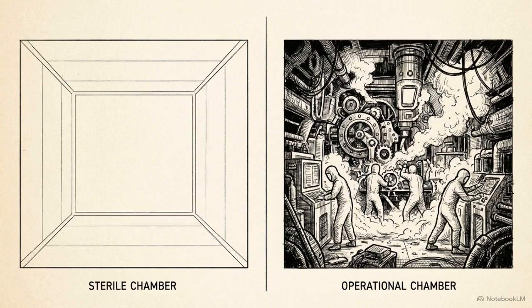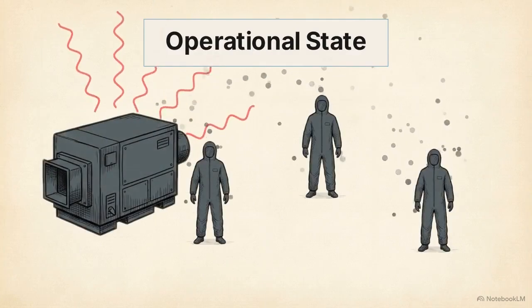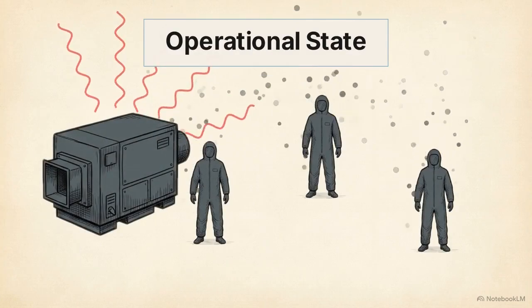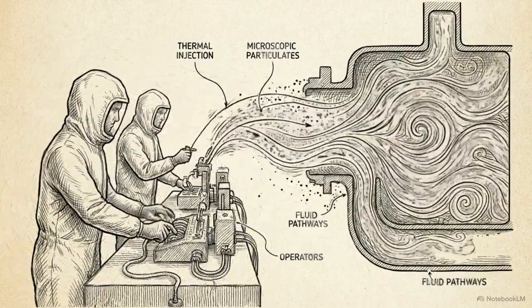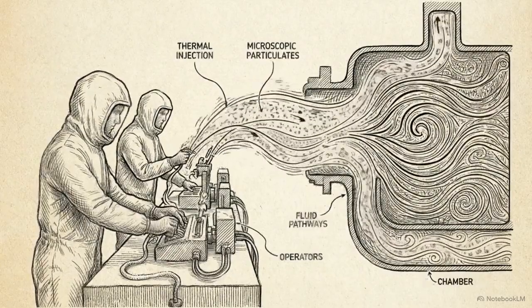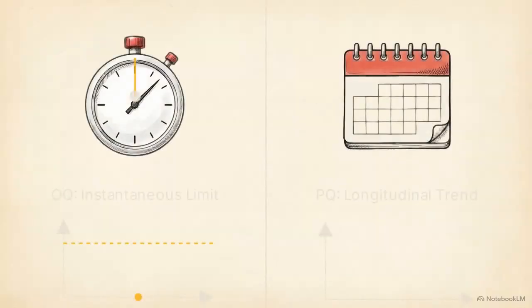Performance qualification, or PQ, provides the real-world equilibrium test. The mandatory environmental state for PQ is the operational state. By introducing active personnel and heat-generating machinery, engineers intentionally inject entropy into the previously static environment. The testing methodology changes here. Whereas OQ relies on instantaneous limit testing, PQ relies on longitudinal data mapping.